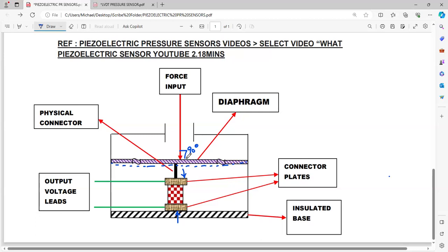So likewise, if this sensor is vibrating like this up and down, the voltage will be continuously fluctuating, and therefore the pressure output will also be continuously fluctuating. So you cannot depend on a correct pressure reading because of the vibrations. That is why you will never find this on board the ship. You will find it ashore, yes.